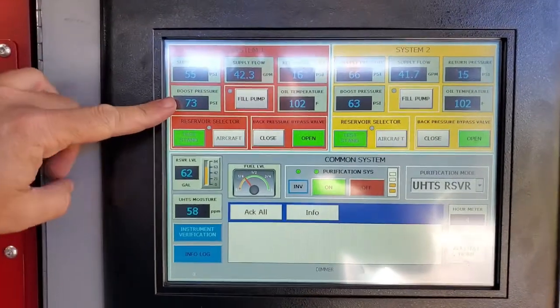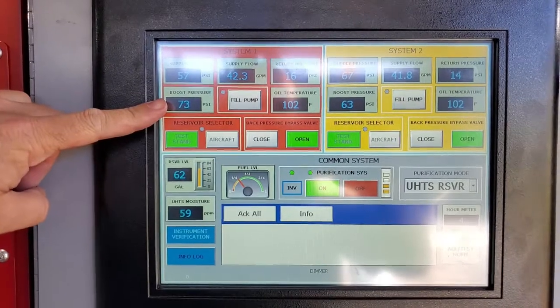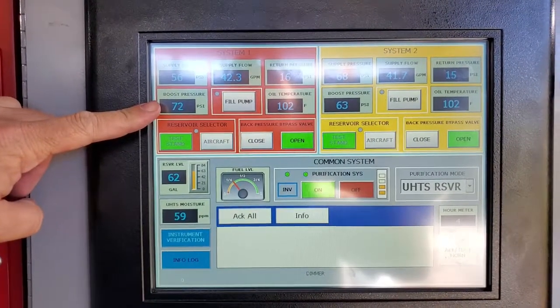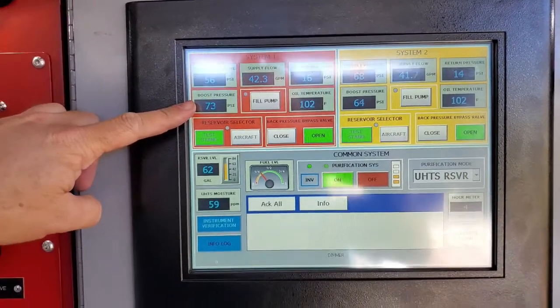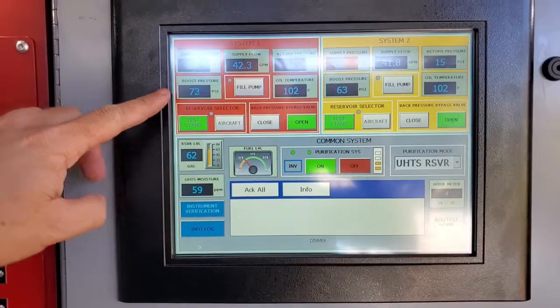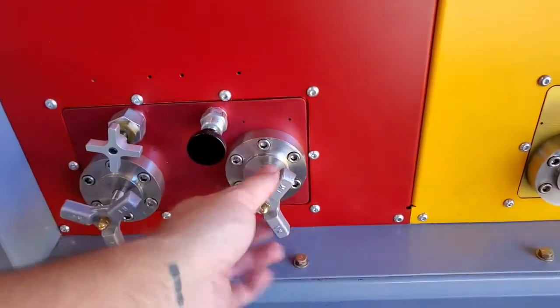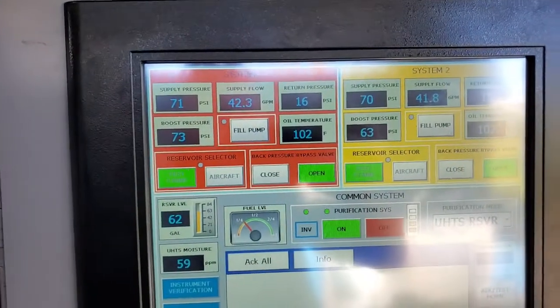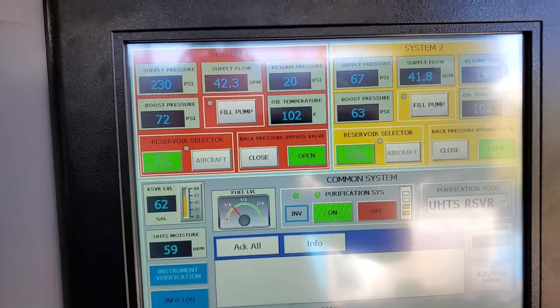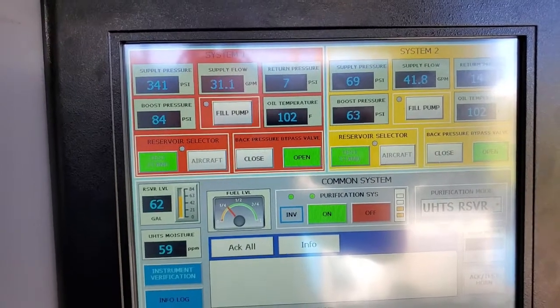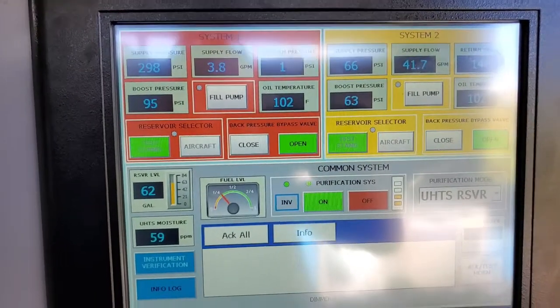You can see here we've got good boost pressure. You want to pay attention if the boost pressure drops below 15 psi, you'll get an alarm and the unit will automatically shut down. Now, as we close the bypass valve, you'll start to see the boost pressure increase, but you'll also see supply pressure increase, which is the standby pressure for the main pump.